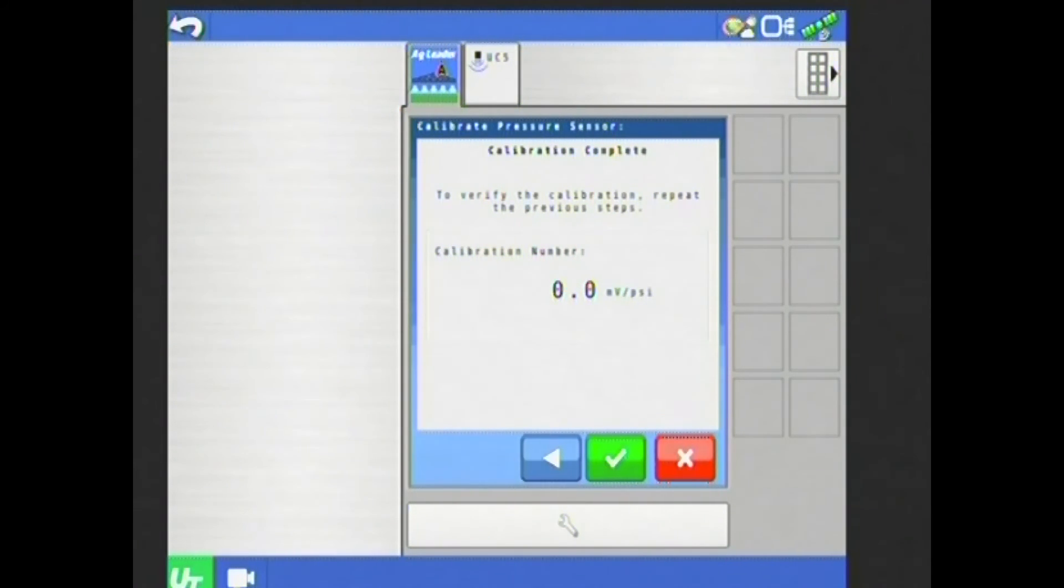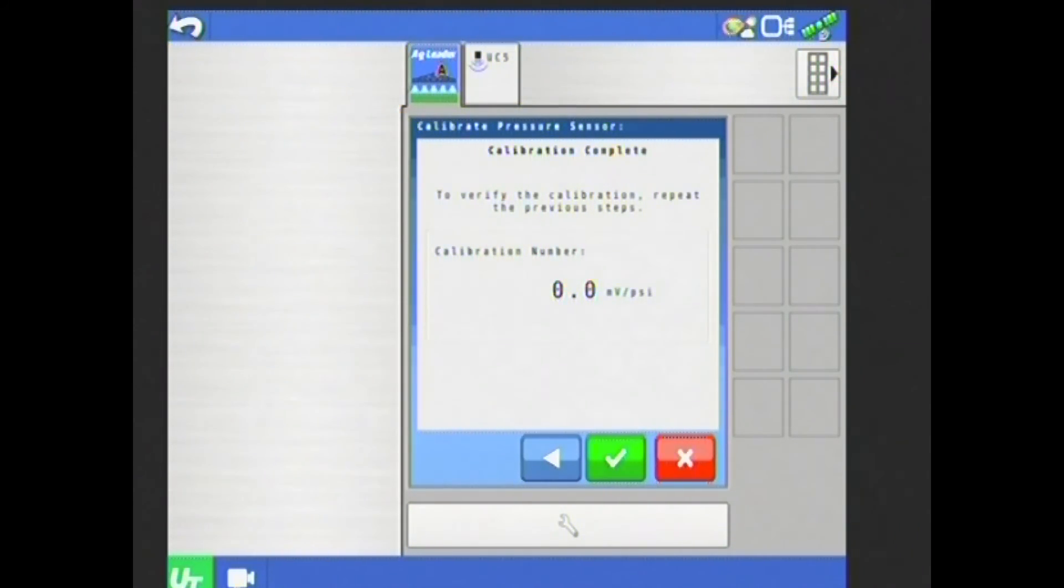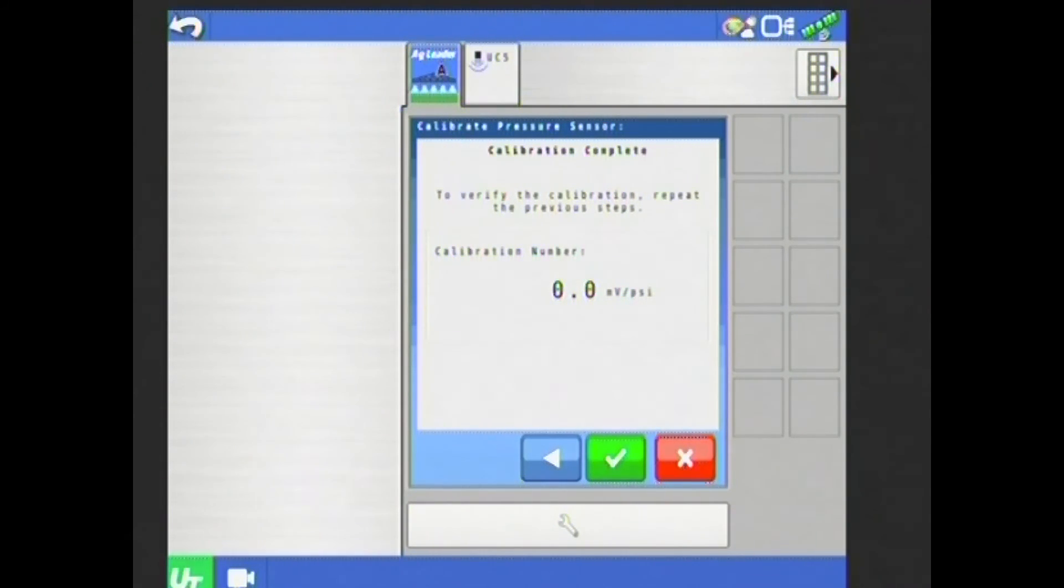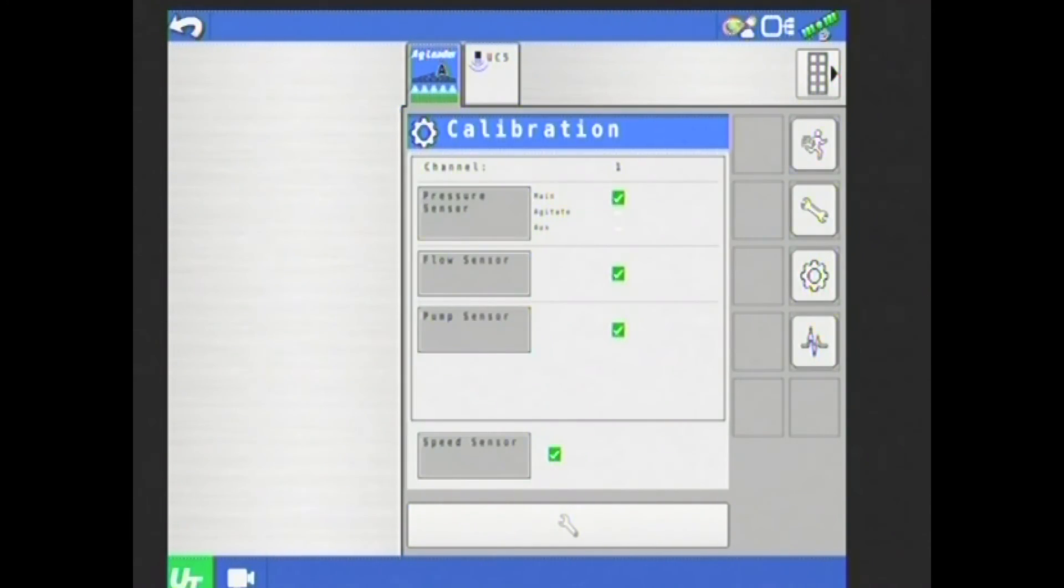My calibration number should be very close to 16 millivolts per PSI. I don't have a pressure sensor tied into the system, so mine will read zero, but yours should be very close to 15 or 16. If it's a little off from that, that's perfectly fine. That's perfectly normal, but it should be pretty close to that 16 number. Hit my green check.